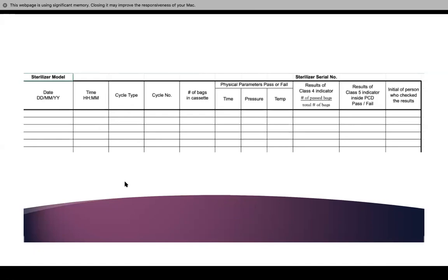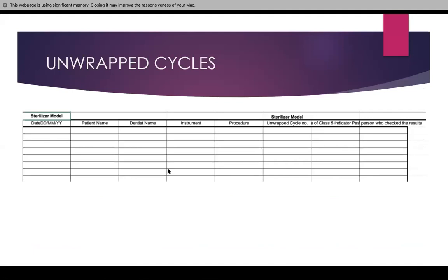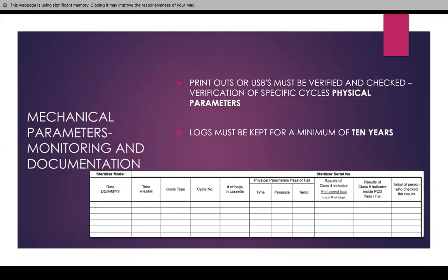Logs are supposed to be kept for 10 years. We also have one for unwrapped cycles and one for the ultrasonic cleaner. We are going to share everything in regards to that. Mechanical parameters such as temperature, time, and pressure — the printouts or USBs must be verified and checked. Logs must be kept for a minimum of 10 years.